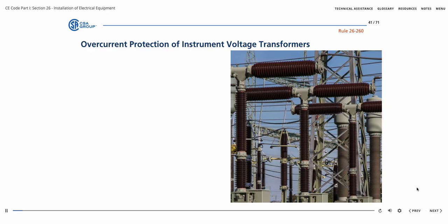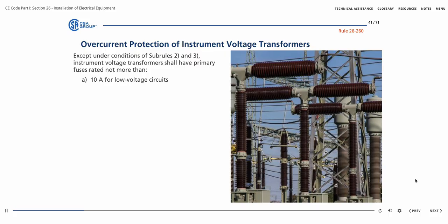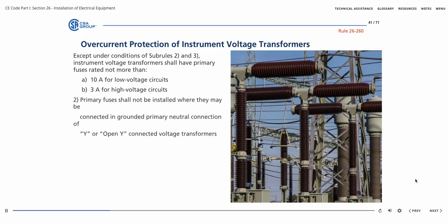Appropriate overcurrent protection for instrument voltage transformers is discussed in Rule 26-260, except under the conditions of Sub-Rule 2 and 3. Instrument voltage transformers shall have primary fuses rated not more than A. 10 amps for low voltage circuits and B. 3 amps for high voltage circuits. 2. Primary fuses shall not be installed where they may be connected in the grounded primary neutral connection of a Y or open Y connected voltage transformers.